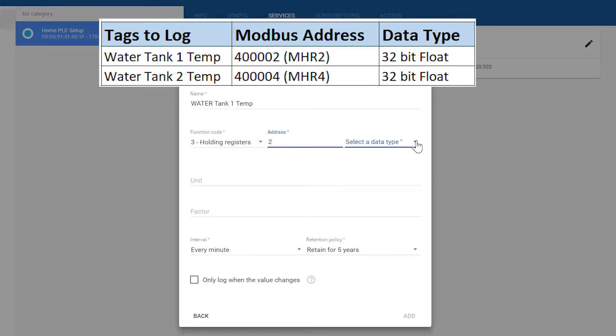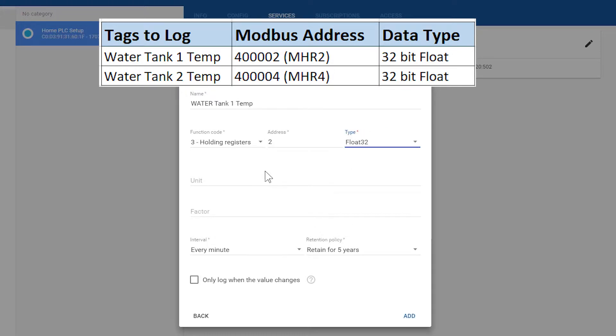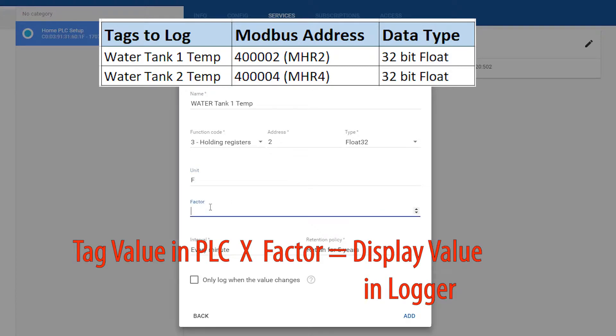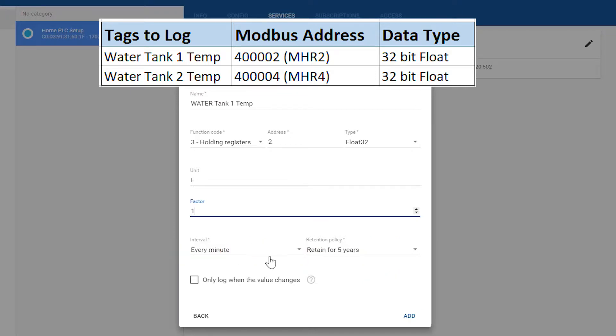As I mentioned before, these are 32-bit floats and their units will be in Fahrenheit. This gives a suffix for the data display. This portion will allow for scaling in the router, but since I have already set up and scaled these tags in my PLC, all I need to do is place a 1 here. For all the other options, I am going to leave them as the defaults. Then select Add.